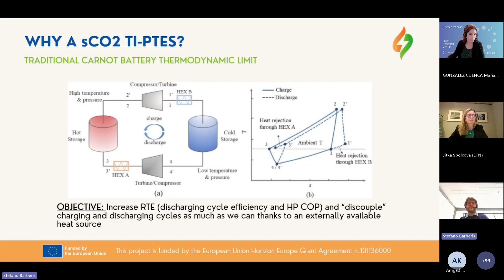So why are we looking at supercritical CO2? Because, particularly with freely available heat sources like industrial waste heat or renewable thermal energy, supercritical CO2 can offer good flexibility and efficiency, both in the power cycle (discharging) and the charging cycle (high temperature heat pump). It also enables the heat pump to operate at higher temperatures than traditional refrigerants, allowing us to store heat at temperatures of 300, 350, even 500 degrees C.